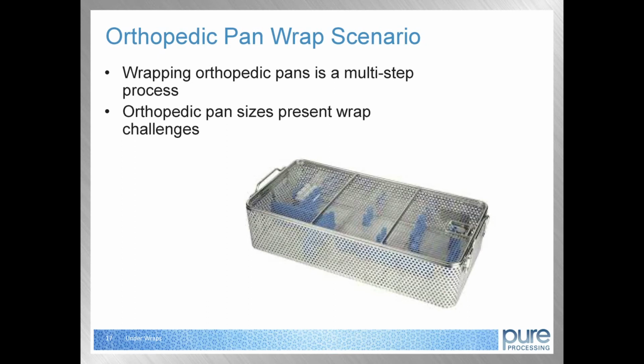Then you hope those pans stay sterile as you slide them onto the sterilization rack. You put them in the autoclave, pull them out, let them set for 45 minutes, take them over to the storage rack, and you hope within those 4 steps that you don't get any holes in the wrap.